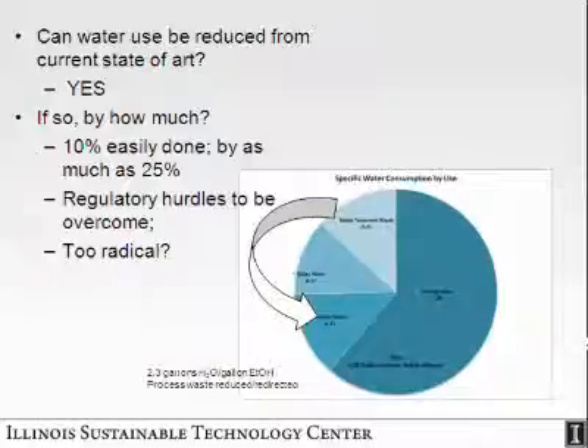The second thing is you have to make sure whatever is being added to the animal feed is considered generally recognized as safe, GRAS status. So you have to start using GRAS status polymers for cooling tower control, so you're allowed to put it back into the processed water. It turns out those polymers are available—a little more expensive than normal non-GRAS polymers, but it can be done. That's the regulatory hurdle you have to overcome.